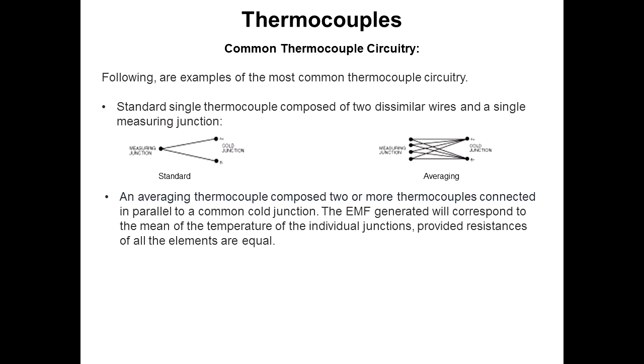Here's a couple of different thermocouples. The one on the left is just a standard one. You have your hot junction where the two wires come together, your cold junction on the isothermal board. Then on the right we have an averaging thermocouple, where you have a series of thermocouples maybe up and down the length of a probe, all going back to a common cold junction. What that does is average the reading all along those different thermocouples. So if you have a 3 or 4 foot immersion, you want to average it all the way across that immersion depth, this is the way to go. So you have 2 or more thermocouples going to a common cold junction.